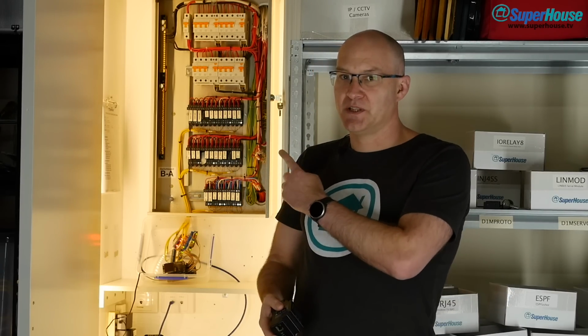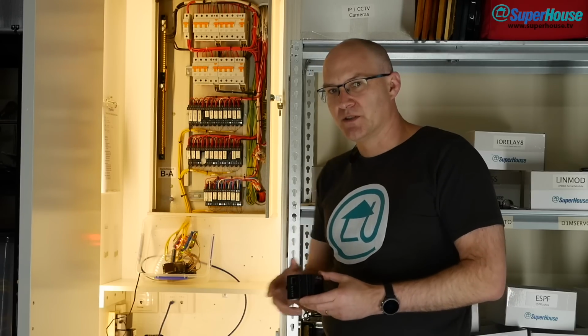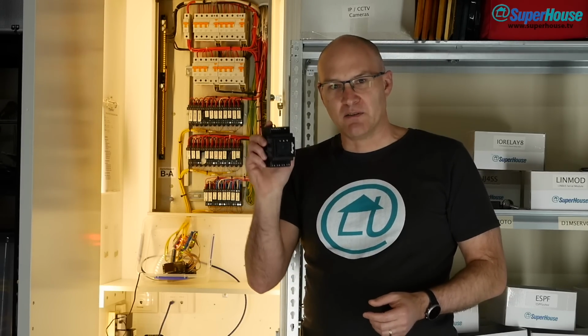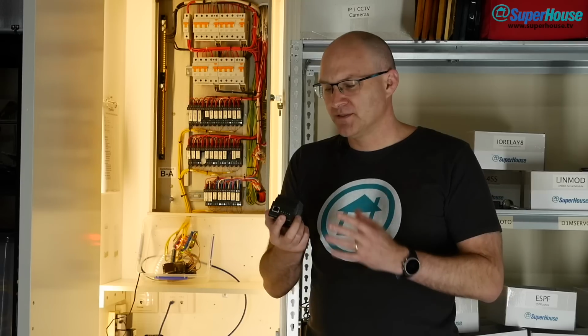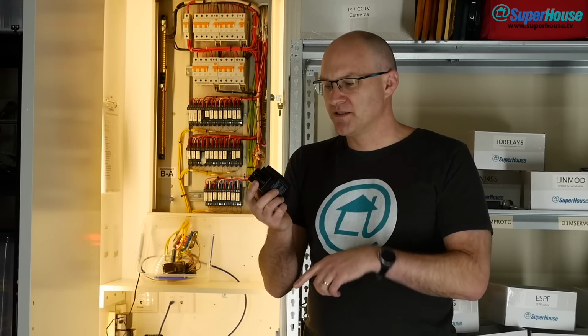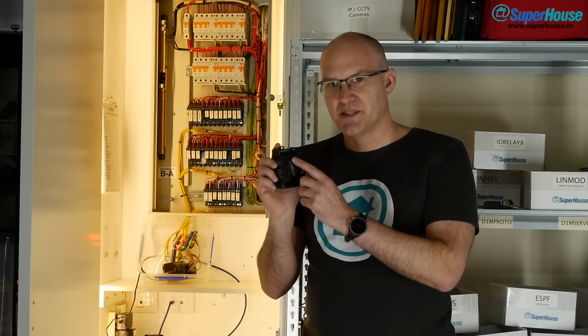If I put eight of them in this switchboard, it would replace all of those relays. It'll take up less space. The controller would go away. I would have power monitoring on every load. And I would have status displays and even local control by pressing buttons on here. So, I mean, it's a no-brainer.